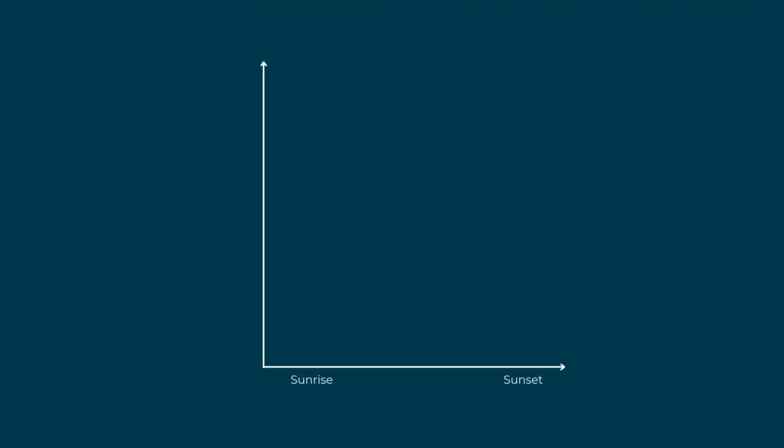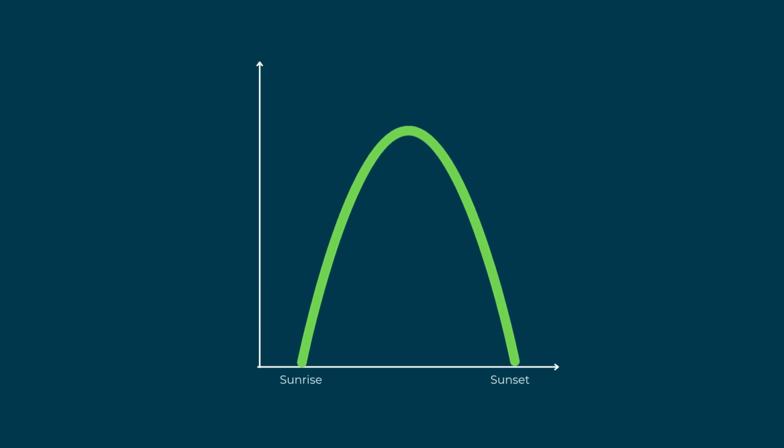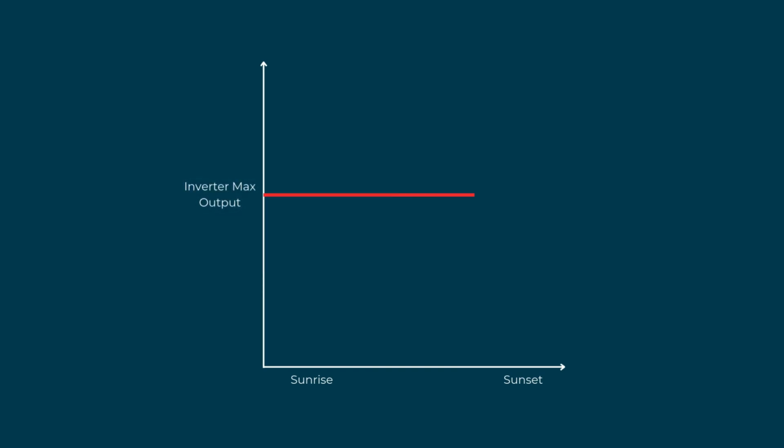When you look at this on a curve, normal solar curves are going to have their energy start in the morning at sunrise and go up like a parabola. It's going to keep increasing throughout the day, peak at that highest point, and then come back down. A good curve is going to be nice and smooth throughout the day. When you have inverter clipping, though, that energy starts to rise and then hits that inverter maximum, and the curve flattens off and then goes back down. It's this flattening of the curve that often panics customers, homeowners and solar providers alike because they think, oh man, how much energy is lost during that?